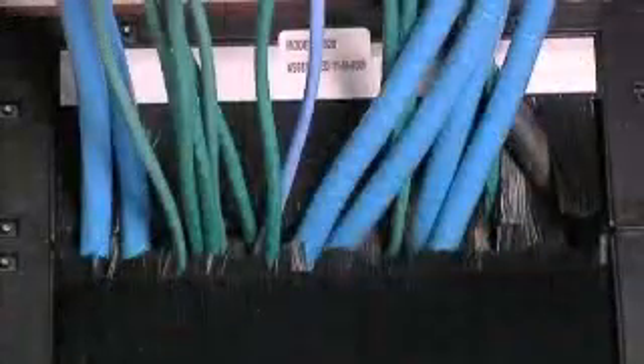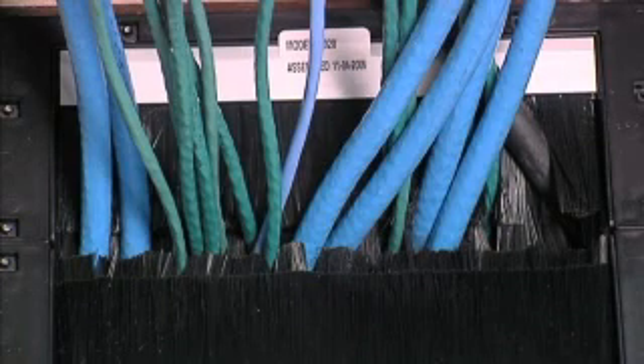We also looked at the cable management. We identified that we needed to use cable trays where possible and to run the cables in the hot aisles, as well as, in running the cables up into the machines, we need to take advantage of and use pillows or brushes to eliminate any loss of cold air on the back of the machines.